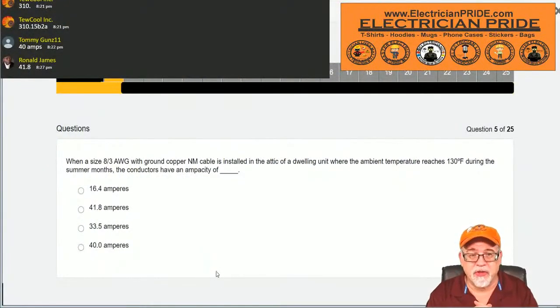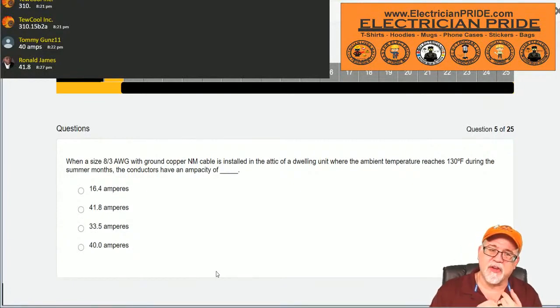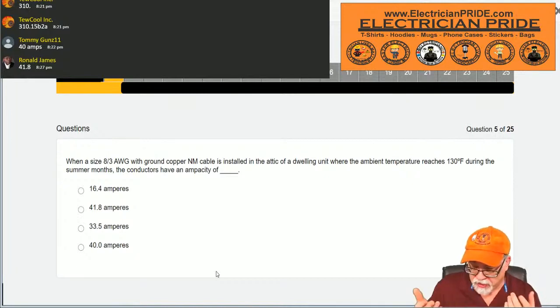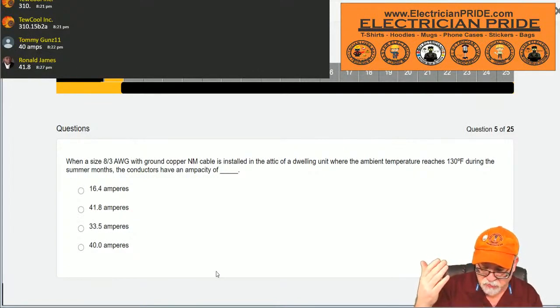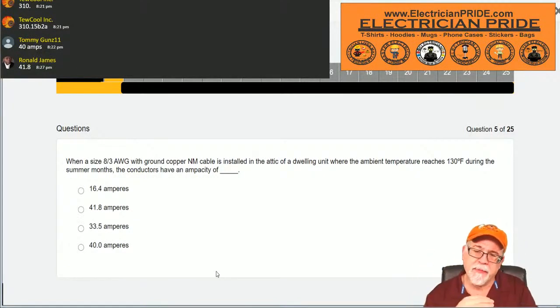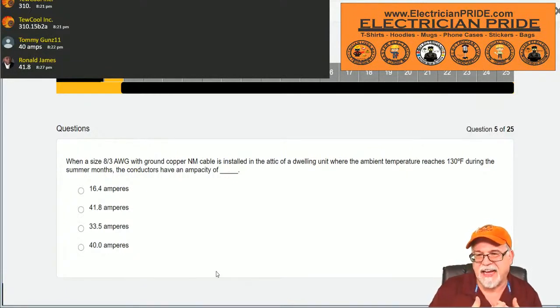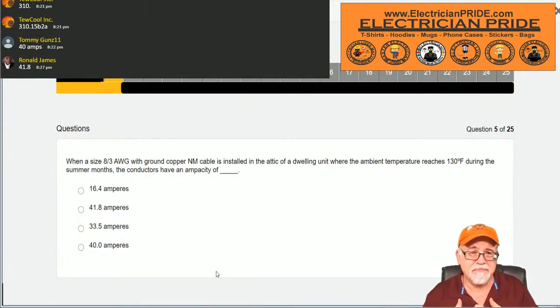Now, what I can promise you is this. On an exam like this, they will give you that 41.8. But let's remember something. The NMB is limited to what? 60 degree column. I can use the 90 for adjustment and corrections, but remember what it said, as long as I don't exceed the value of the 60 degree column. Now, the conductor, even after adjustment and correction, theoretically could handle 41.8 amps, but remember, you can't exceed the value of the 60 degree column.